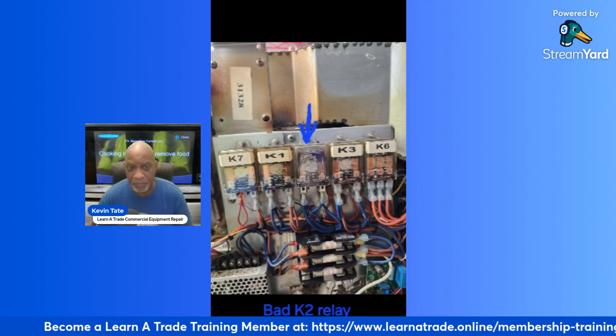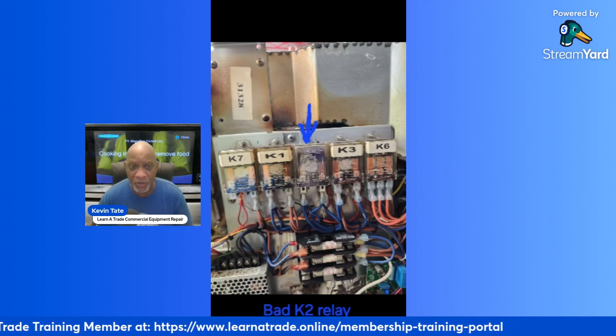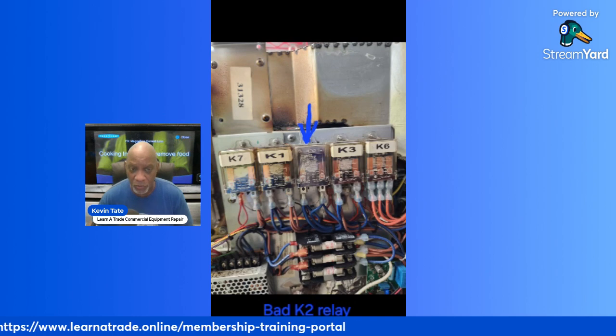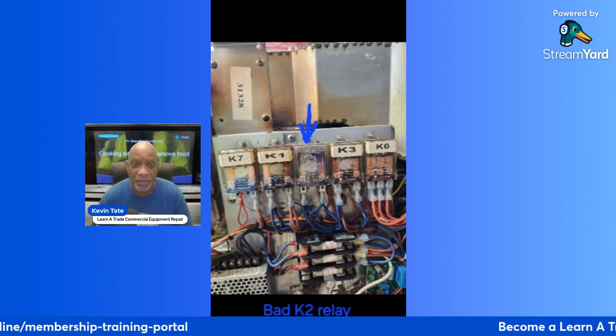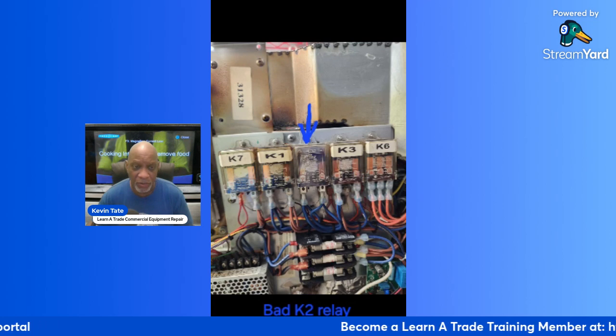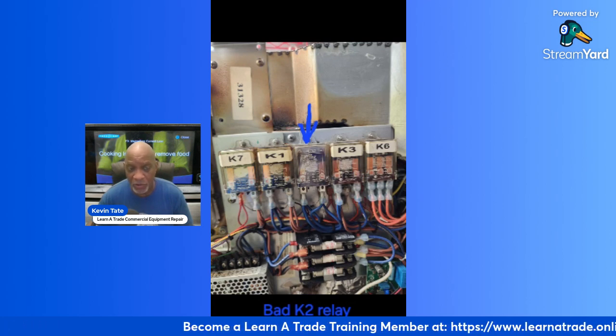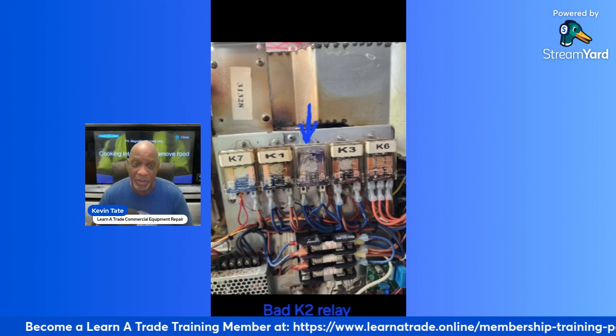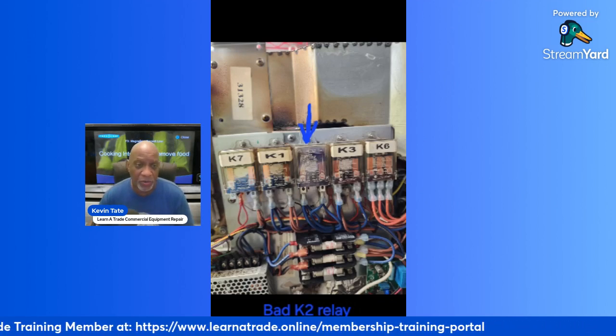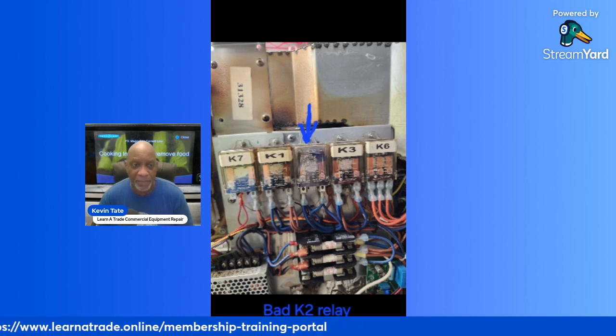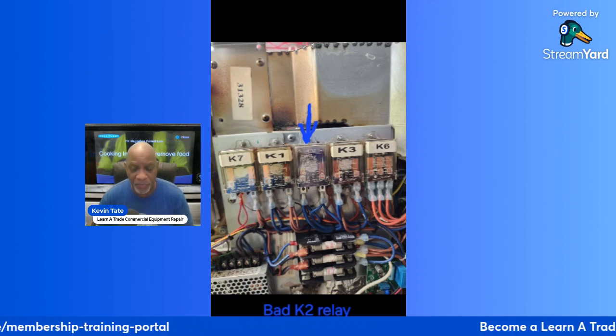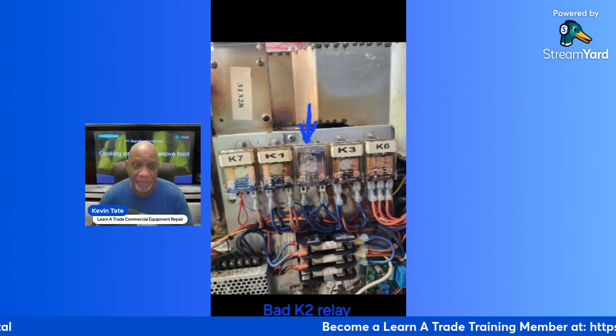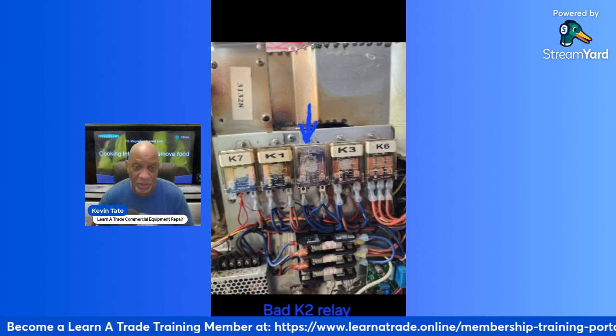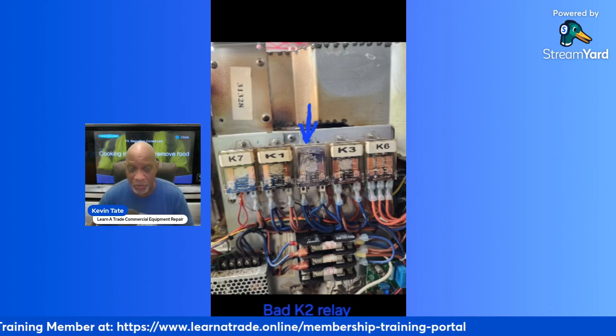This is one of the first things you want to look at, your K2 relay. Take that right side panel off of the oven and you'll see it right there. Unless it's a newer model; this is an older model. If it's a newer model, like one of the bullet models, then your relays won't be on the right side. They'll be up top, connected into the circuit board, and you can't miss them. You just take the top panel off and you'll see them. That's on the bullet unit, but this unit here is an Encore unit. It's an older unit, and the relays are all on the right side.